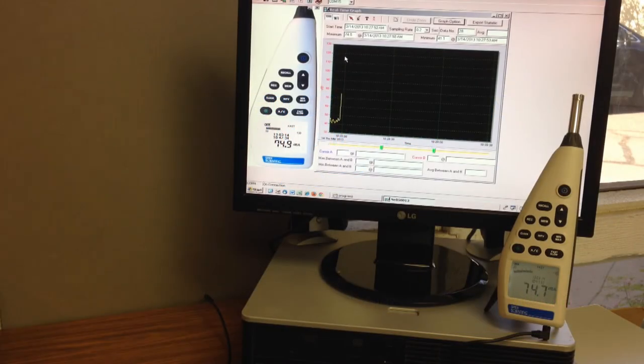A single dynamic 30 to 130 decibel range eliminates the need to manually select ranges and prevents data errors during range changes in auto-ranging models. All test parameters are simultaneously displayed on a large, bright, backlit display featuring 0.1 decibel resolution and a bar graph.